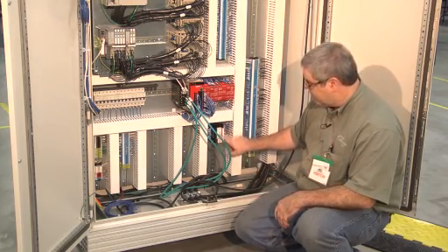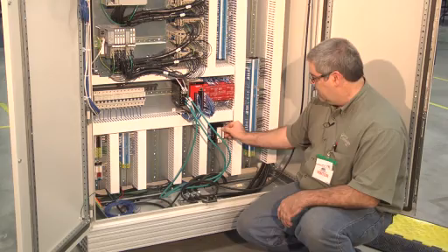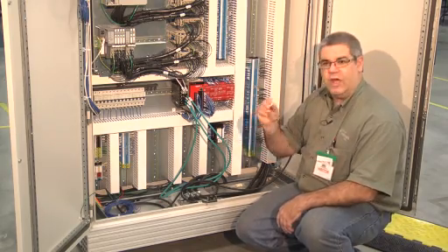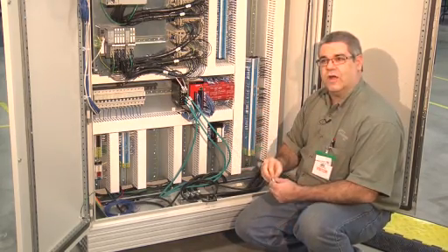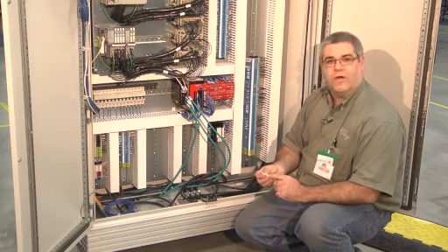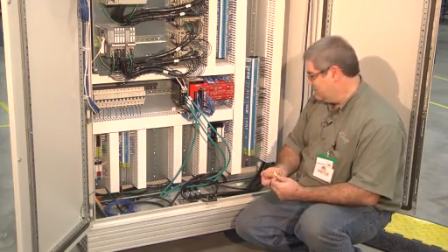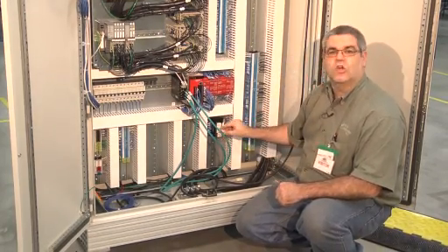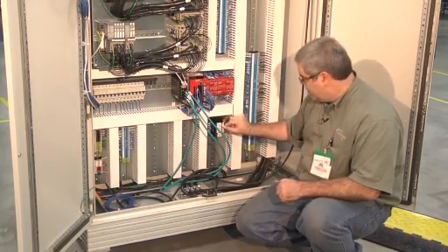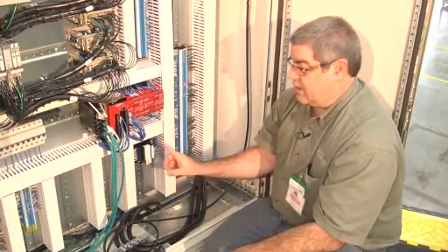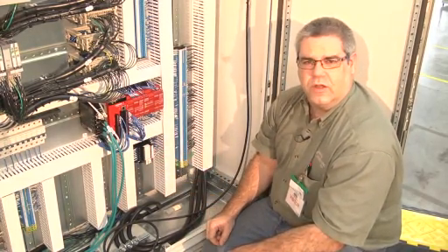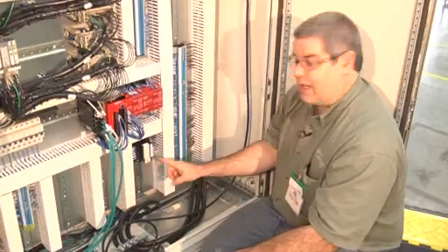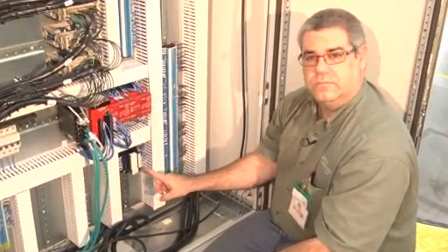This is internal terminal relays that are purposely removable, and they're unlabeled so that you can't see what they are. So you can cut pins off on them and stick them in and have problems. They don't have an indicator light if they've actually worked. There's only an indicator light that the coil has been fired from the PLC. And there's a couple different types of relays that are used in here, and I'd like to show you where the other style is used right here on this panel.